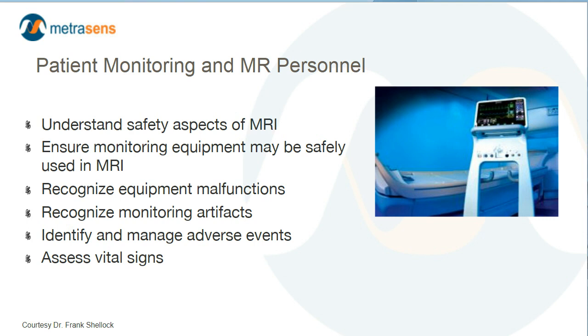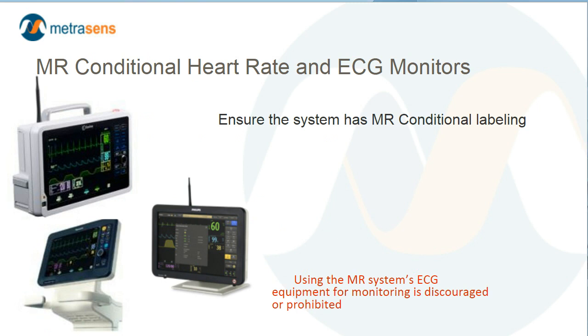In whatever monitoring system you choose, it's important to ensure that it is a system which has been designed for use in Zone 4 and that the manufacturer has tested it and properly labeled it as MR conditional. It's also important to point out that an MRI system's EKG hardware and software is designed for data acquisition purposes and cannot be used for the physiologic monitoring of a patient. In many cases, the MR system's user manual will clearly state that the ECG components are not to be used for physiologic monitoring of patients.